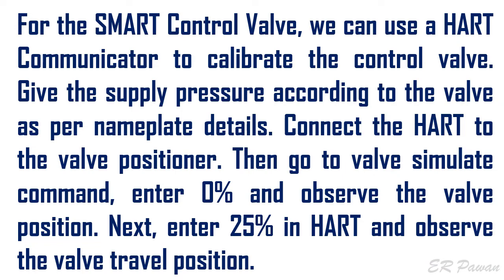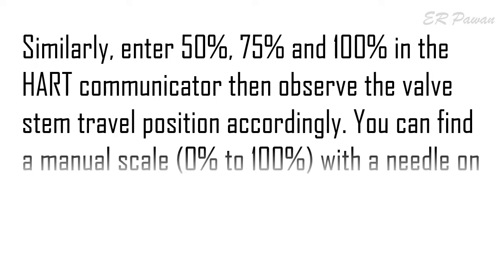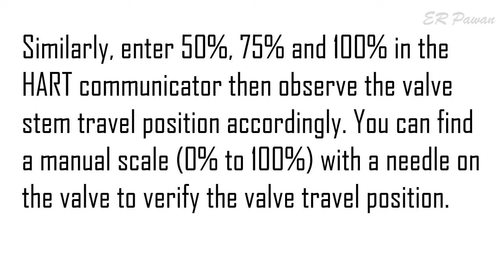Then go to the valve simulate command, enter 0% and observe the valve position. Next, enter 25% in HART and observe the valve travel position. Similarly, enter 50%, 75%, and 100% in the HART communicator, then observe the valve stem travel position accordingly. You can find a manual scale from 0% to 100% with a needle on the valve to verify the valve travel position.